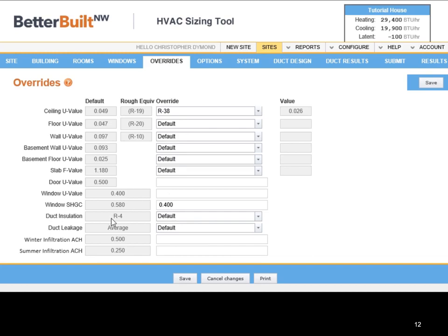In the Northwest, you'll generally find that the U value and the solar heat gain coefficient march right along. If you happen to buy a class 30 window, chances are the solar heat gain coefficient is going to be about 30 also. That can make a very big difference on the cooling load.